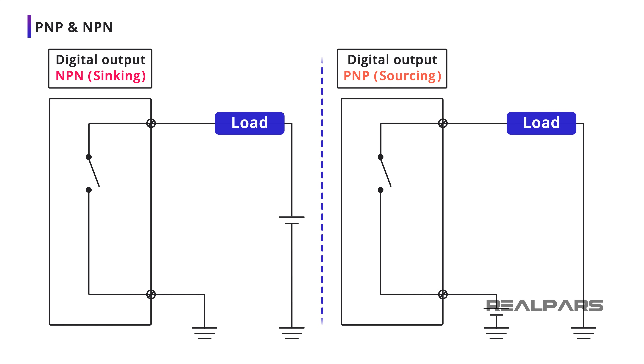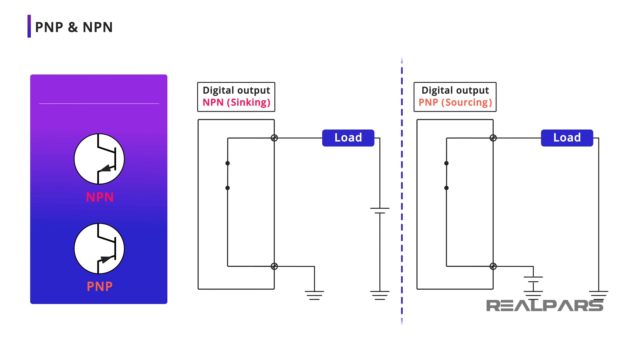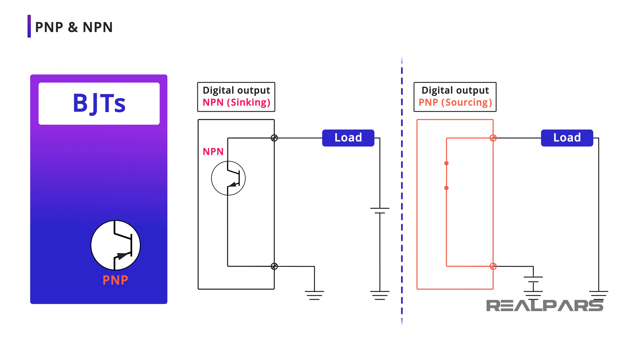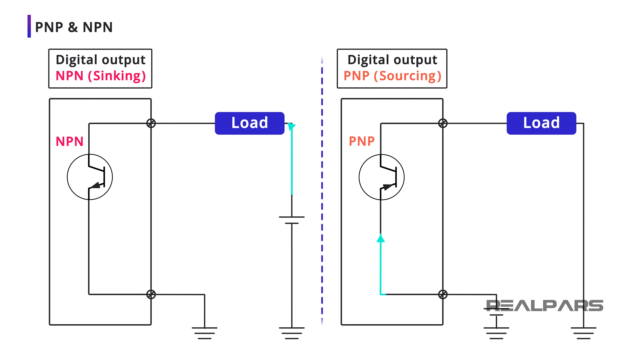Why are the names PNP and NPN used? Whether it's sinking or sourcing, an output module must act as a closed switch to complete the circuit. In many output modules, the actual switching is performed by bipolar junction transistors, or BJTs. In a sinking module, the transistor is an NPN. In a sourcing module, the transistor is a PNP. The current flows into a sinking module, and out of a sourcing module.